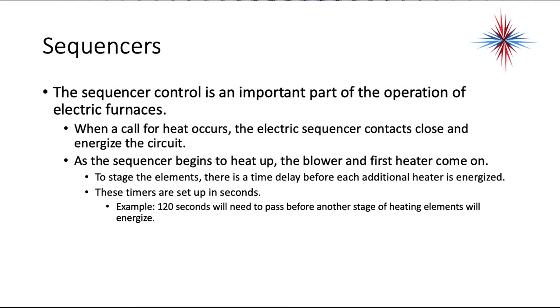The sequencer control is an important part of the operation of electric furnaces. When a call for heat occurs, the electrical sequencer contacts close and energize the circuit. As the sequencer begins to heat up, the blower and the first heater come on. To stage the elements, there's a time delay before each additional heater is energized. The timers are set in seconds. For example, 120 seconds will need to pass before another stage of heating element will energize.